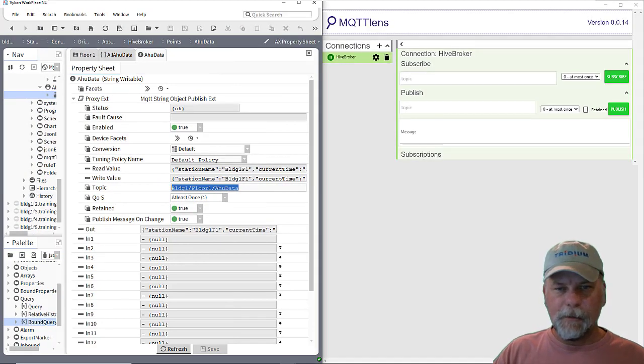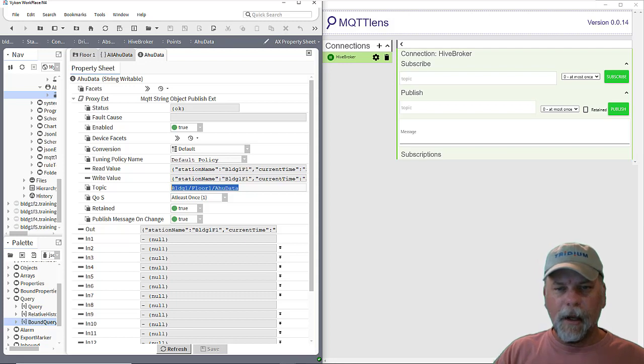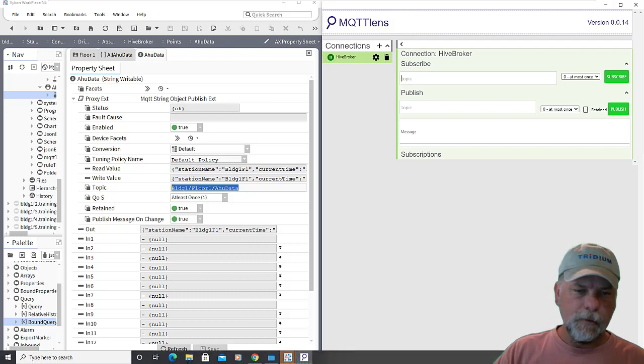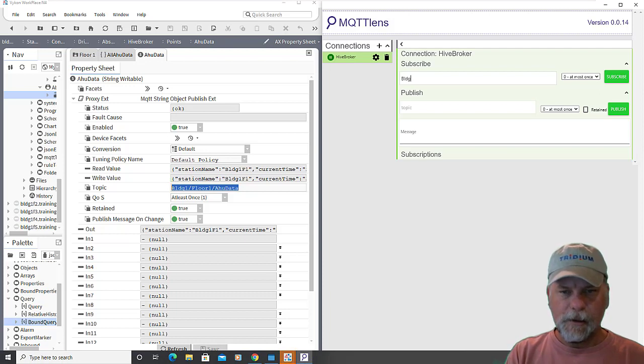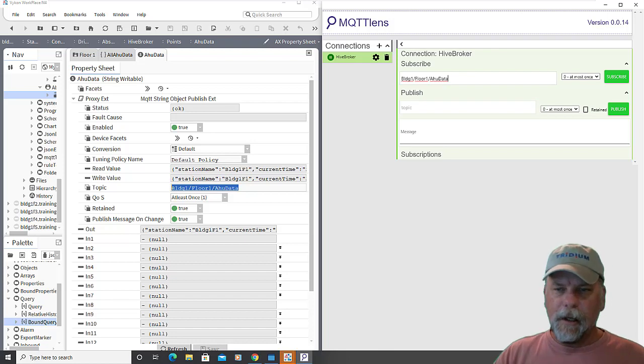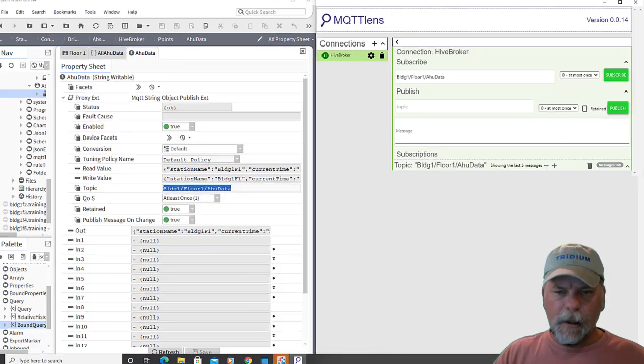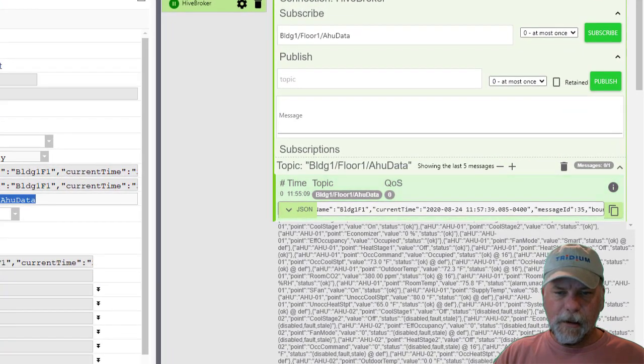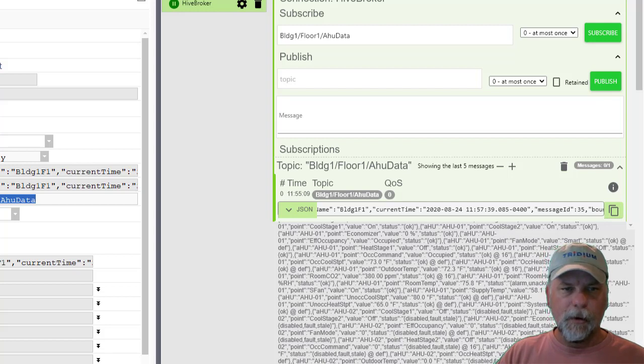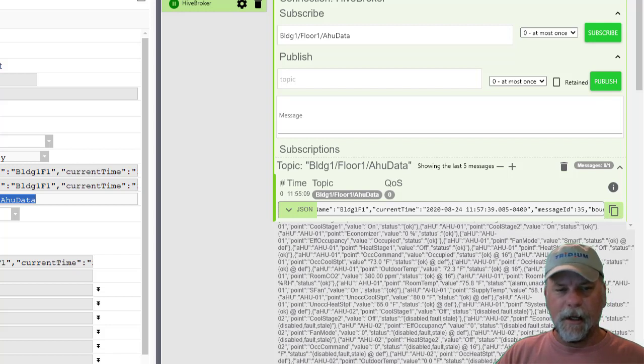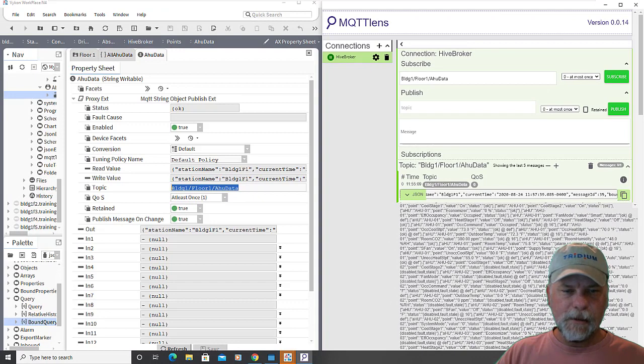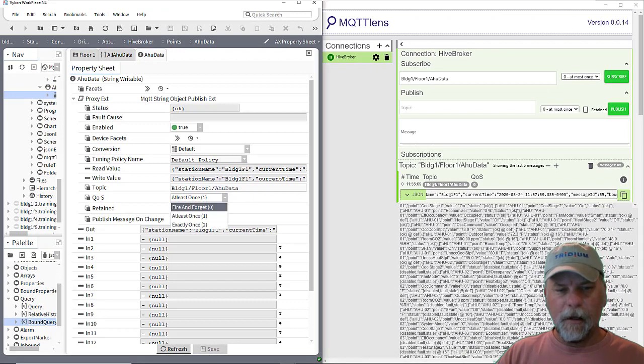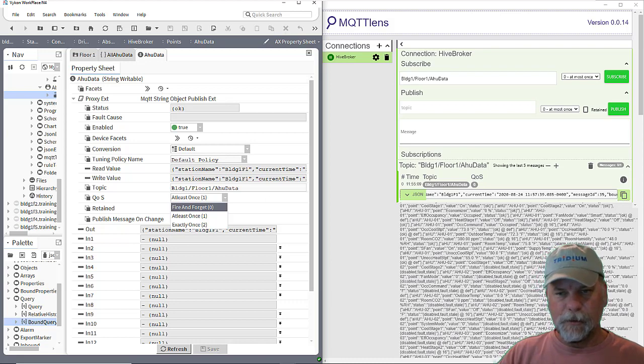And in this case, I'm using just a MQTT lens broker or client rather is connected to the same broker. And I can subscribe to a topic there, which would be the Bldg1 slash Floor1 slash AhuData and subscribe to that topic. And you can see here that then the client receives the message from the broker. So the station published the topic to the HiveMQ broker and any other clients that connect to it should be able to retrieve that message asking for it. And if I was only set on fire and forget, then the client would have to wait until the next time that I publish it.